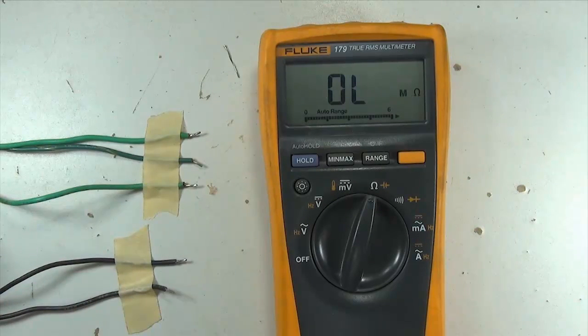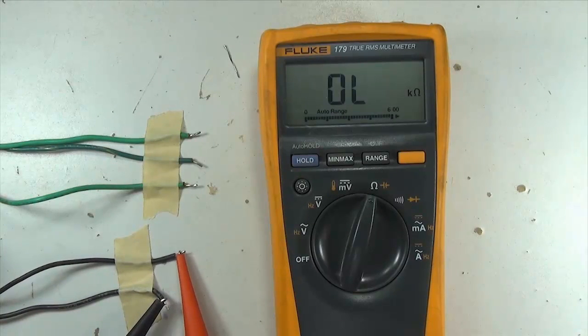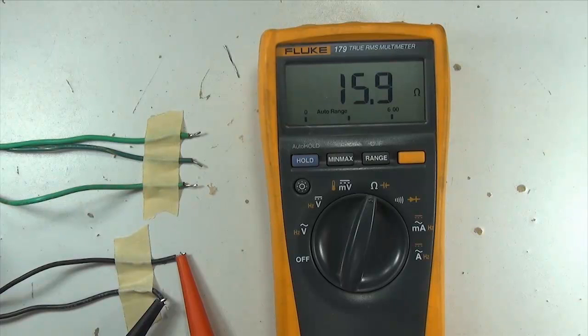Now let's measure the resistance of the primary winding. So we'll carefully connect to the two black wires on the primary side of the transformer. And here we have about 15.9 ohms on the primary side of the transformer. That doesn't look too bad.